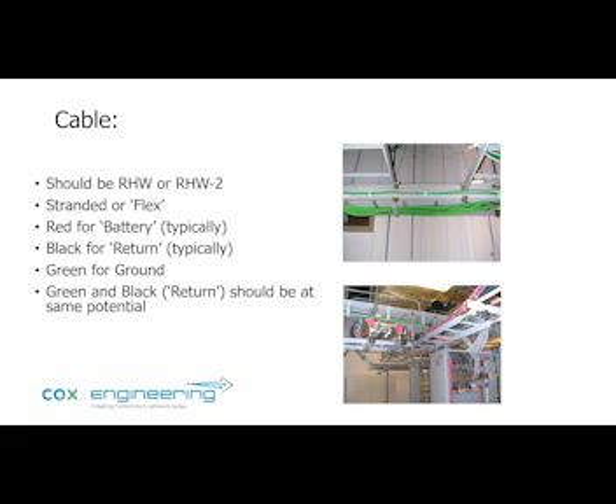Well, that's because everyone's used to the automotive industry where you have a negative ground in your vehicles. But when you have negative 48 volts, you have a positive ground. So the negative is red and the positive is black. So the way to think about it is that the red should always be hot, whether it's negative or positive, and the black should always be the return or the neutral or the at ground potential, let's say, right? But again, not all the manufacturers do that. You'll get equipment that has these colors, and so don't go by the colors. Just use your meter. That's the moral of the story.